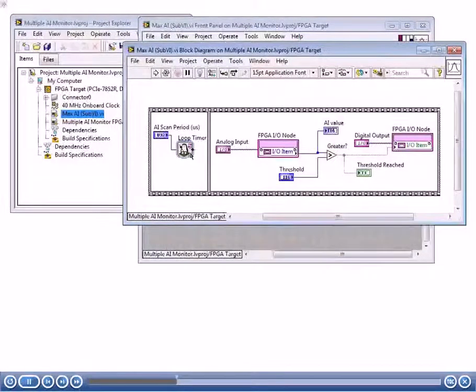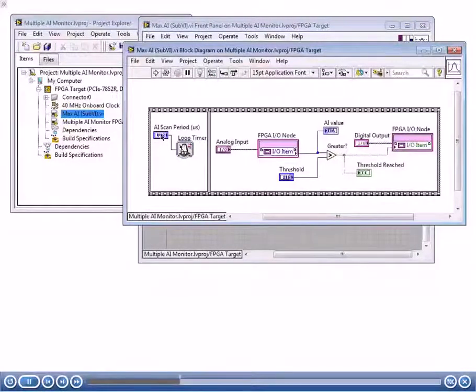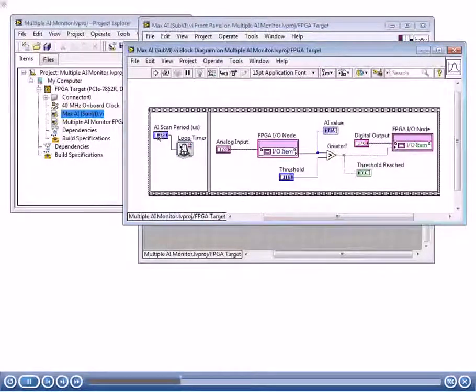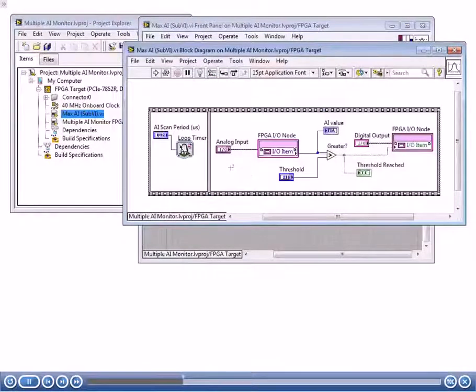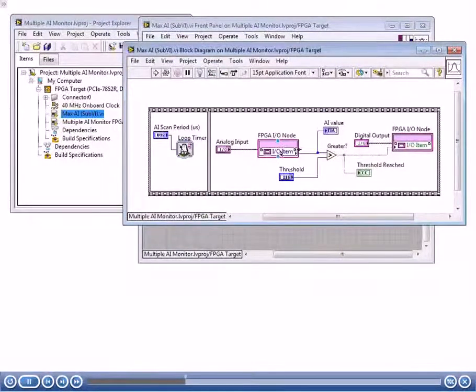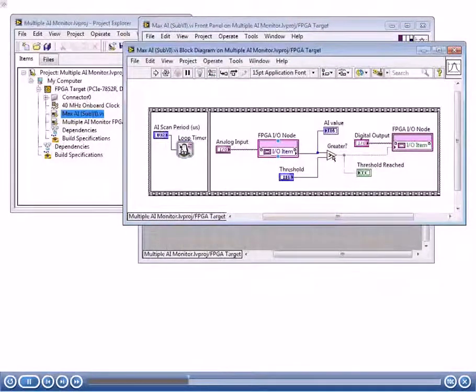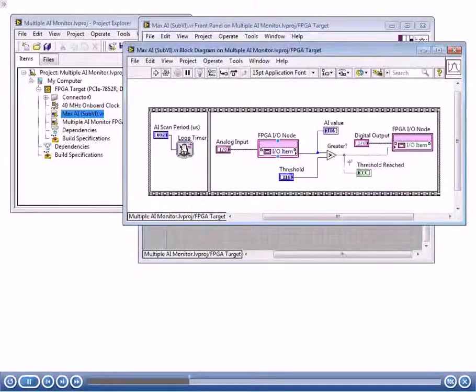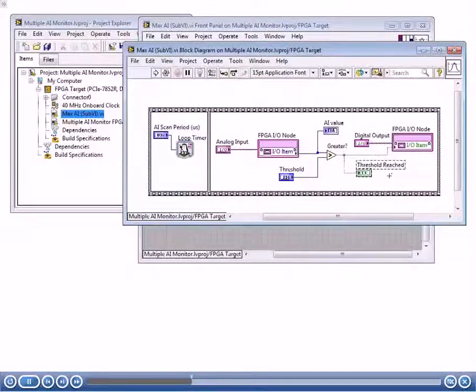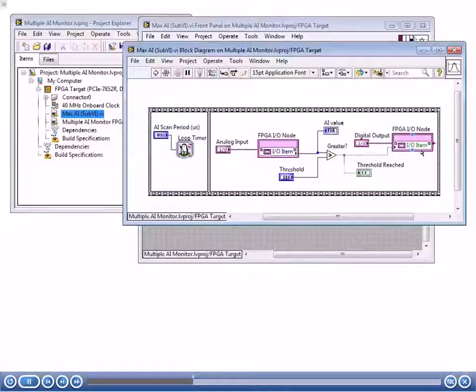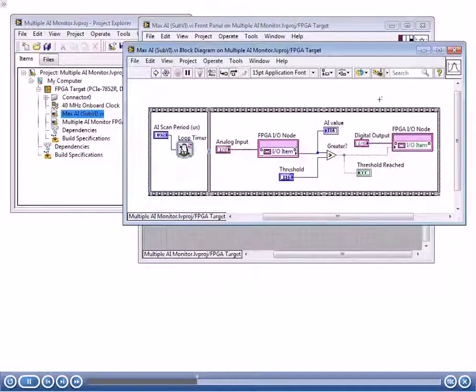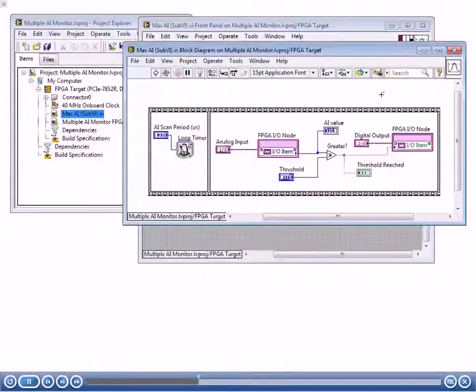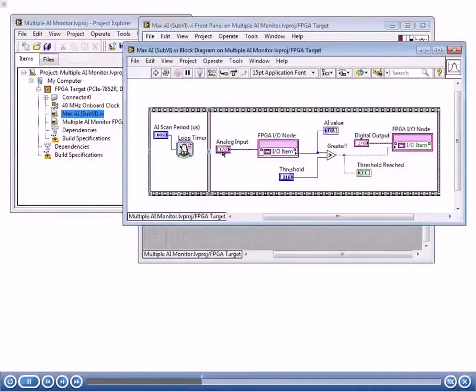Here we have a loop timer. We're going to be able to tell it what loop rate to run at, so that's our AI scan period. Then we're going to take a look at the analog input, extract the IO from that, compare it and see whether the threshold was reached yet. We're going to output whether the threshold was reached to an indicator, and we're also going to output that result to a digital output, which is specified by this FPGA-IO control. Because we have this as a sub-VI, we can reuse it with several different digital output and analog input channels.